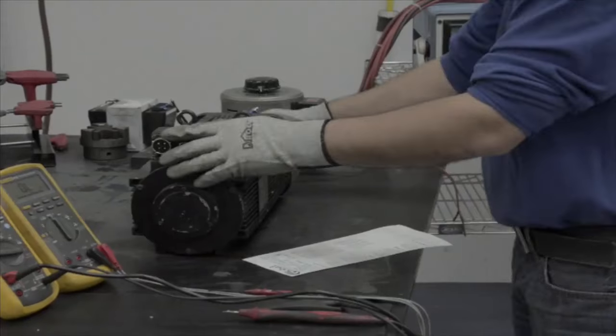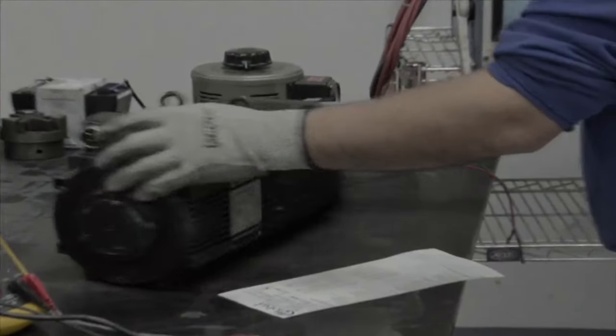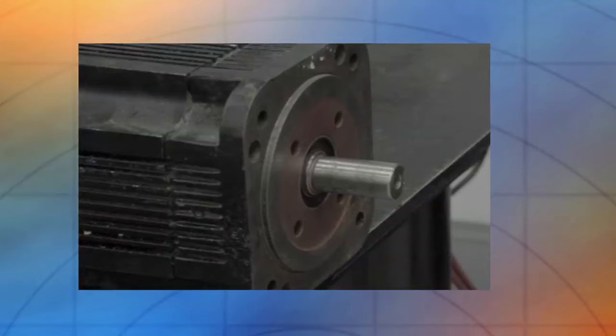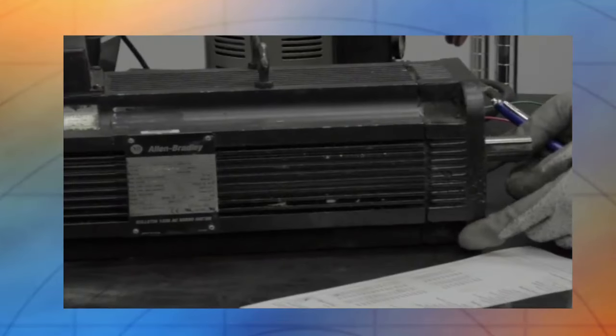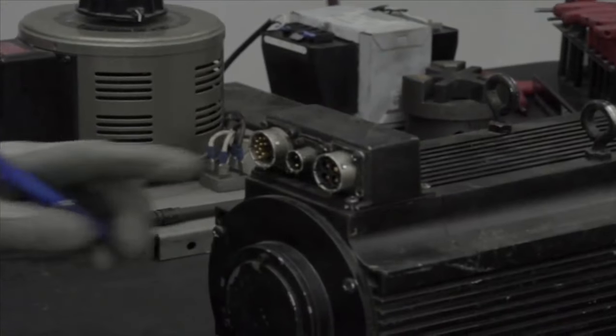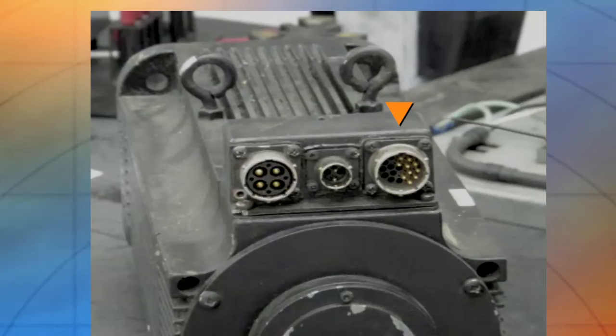Now that these are verified, the tech is visually inspecting the servo motor shaft, keyway, front end bell, back end bell, terminal box, feedback connector, brake connector, and three-phase AC connector.